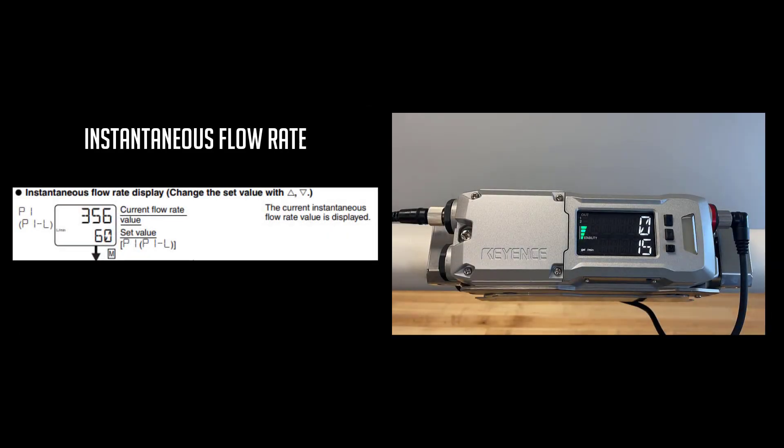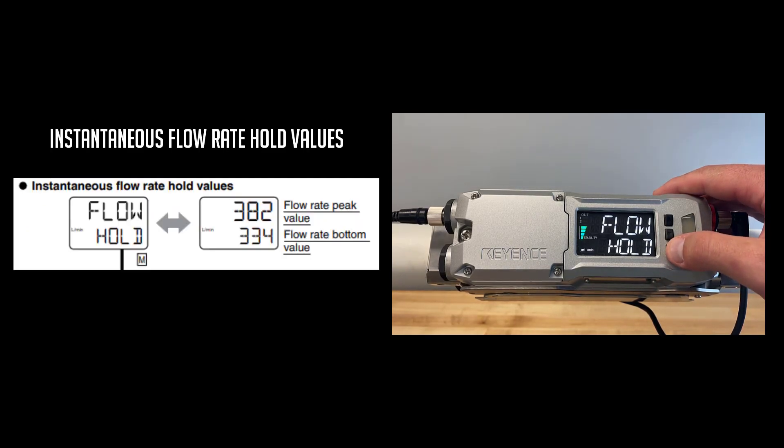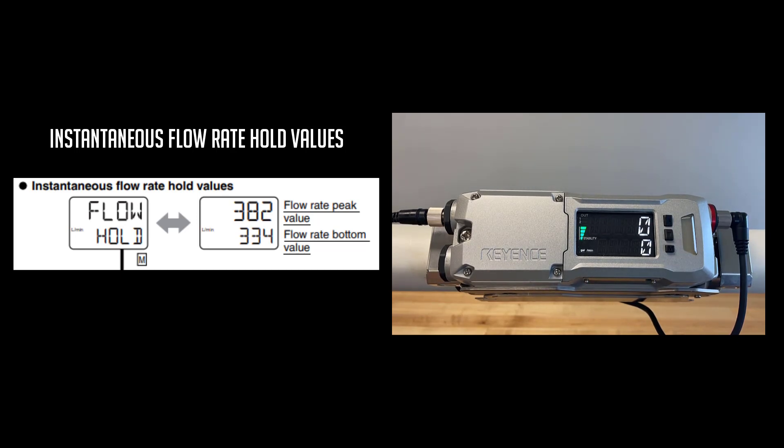By default, the unit will be set to the instantaneous flow rate display screen, where the bottom number is your threshold and the top number is your current flow rate. Tap mode to switch displays. Here we can see hold values where the top number is your peak instantaneous flow rate, and the bottom number is your bottom instantaneous flow rate at a given time.